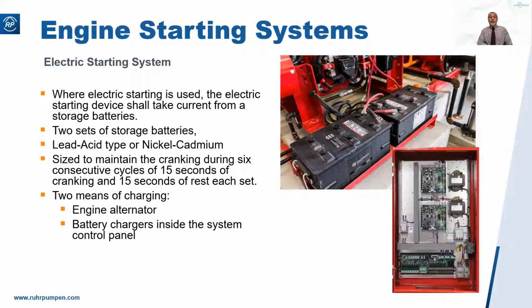Batteries, most commonly onshore, would be lead acid type. Offshore, it's very frequently nickel cadmium type. And again, as I mentioned before, they have to be sized for the 6 start attempts of 15 seconds each. They would be recharged by the engine alternator, but also by 2 battery chargers inside the control panel.